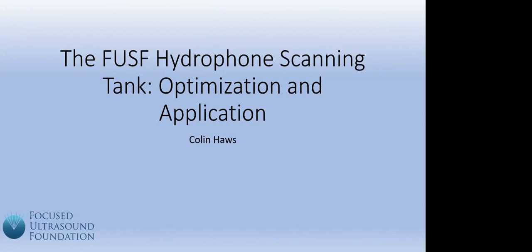The reason I'm asking is because I've implemented such a system in the Insightec body system, which is a built-in function that technicians use in order to scan the well-being of the transducer. And there we finish a complete scan at 100 micron resolution in something like 5 minutes. The trick for doing that is having a gating mechanism so we never stop the transducer motion. We just have a gate signal that lets us capture the hydrophone signal in real time with almost zero delay. But even if there is a delay, it's a constant delay that can be compensated for. So I don't know if you use that trick in that system, but feel free to borrow it, steal and implement.